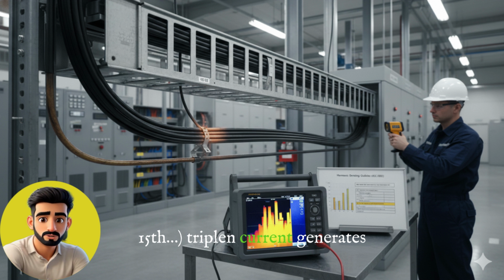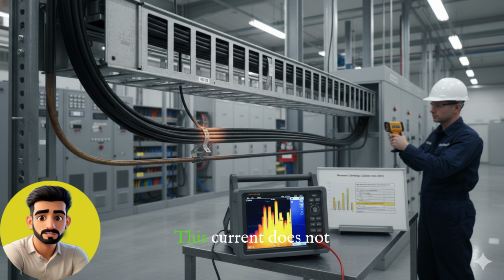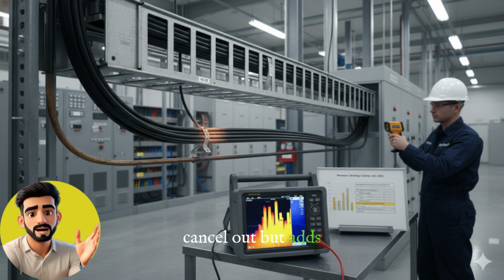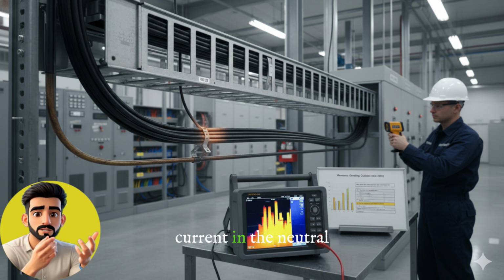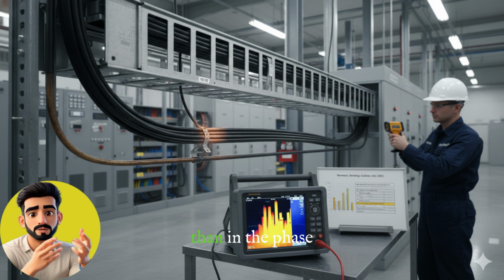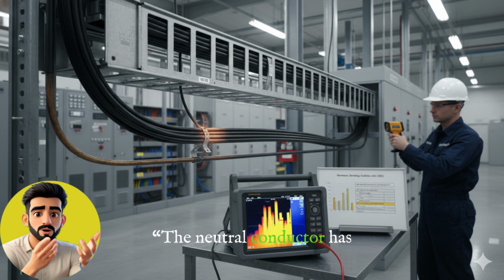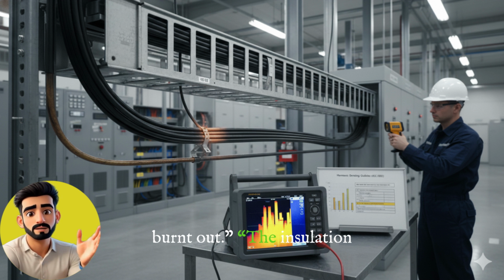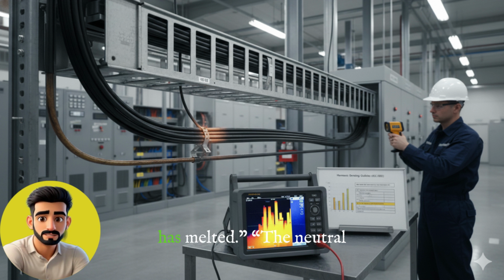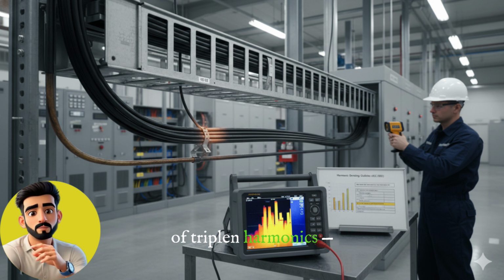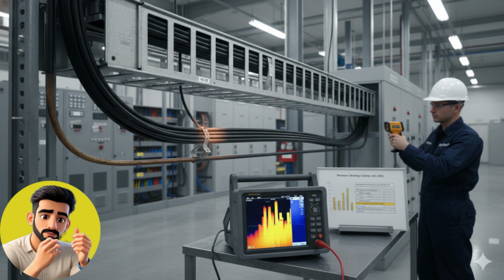Triplen current generates in the neutral. This current does not cancel out, but adds up, meaning the current in the neutral conductor can be more than in the phase conductor. You may have heard, the neutral conductor has burnt out. The insulation of the neutral cable has melted. The neutral lug has turned black. All these happen because of triplen harmonics, not overload.